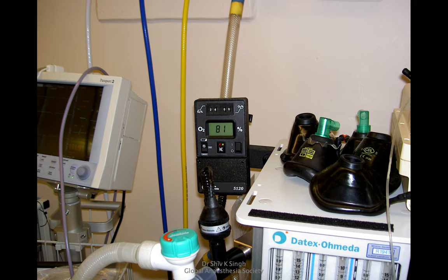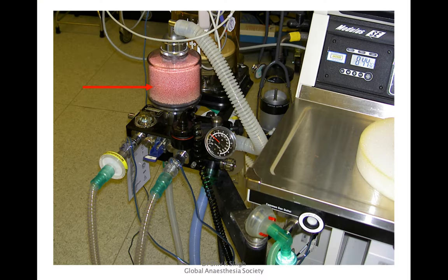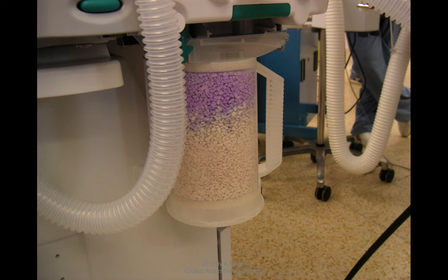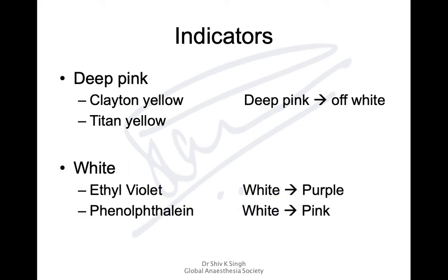Oxygen analyzers are a very important integral part of modern machines. You also attach a breathing system, including circle systems that use soda lime. You should know the constituents of soda lime and the reactions that occur when carbon dioxide contacts it — how heat and water are generated, maintaining humidification and temperature. Know the indicators: Clayton Yellow and Titan Yellow (or Ethyl Violet which turns from white to purple, and Phenolphthalein which turns from white to pink) to determine when soda lime is exhausted.